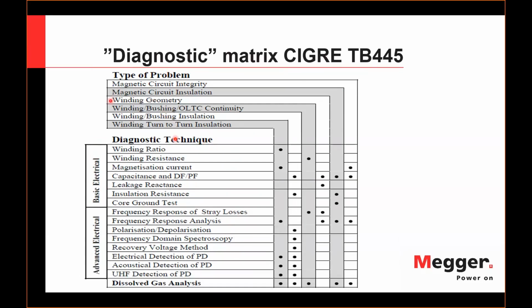A transformer might have different problems, starting with the magnetic circuit, and electrical ones: windings, bushings, tap changer, contact problems. Inside the winding, there could be interturn shorts or opens. All of that must be diagnosed and found to assess the condition properly. And there is not one single method that will provide the answer to any question. There are a number of them, so we're talking about an integration of those methods to make a system.